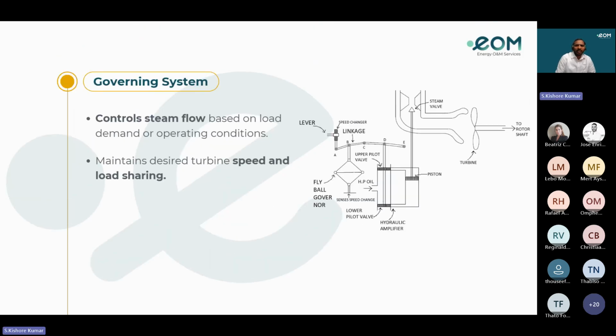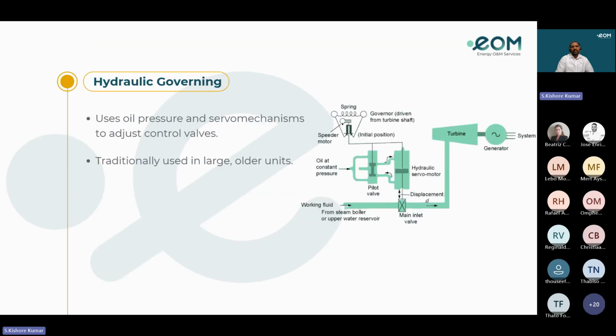Coming to the governing system, hydraulic or electronic governing system. It controls steam flow based on load demand or operating conditions, so it maintains the desired turbine speed and load sharing. The hydraulic governing system uses oil pressure and servo mechanisms to adjust control valves, and it is traditionally used in larger and older units, like the flyball. The steam will enter based on the differences in speed. The flyball will operate and the hydraulic governor will give signals to the control valves, and they will open and close. Based on that, the RPM will increase or decrease.